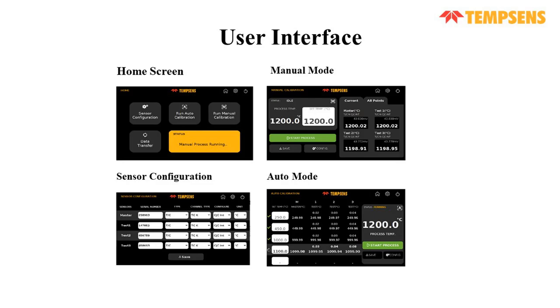For the manual mode, you need to specify a particular temperature one at a time. As you can see, it is at 1200. Once 1200 is completed, you need to set another temperature. For the auto mode, 5 temperatures will be set, and you don't need to look at it again and again. Once it is completed, you can just save and the process will be completed. As you can see, once a temperature is completed, there will be a green right tick on the left, and then it will move on to the next temperature without manual interruption.